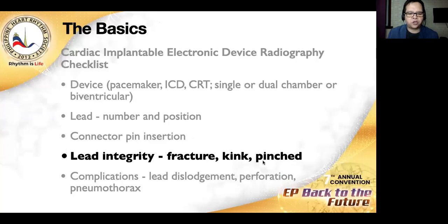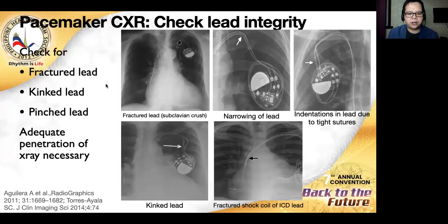Now, lead issues, specifically lead integrity, are also commonly assessed by X-ray. So whether you're looking for fracture, kinks, or a pinched lead, that can be assessed by the X-ray. So the checklist includes looking for a fractured lead, a kinked lead, or a pinched lead. And for this, it is imperative that adequate penetration of the X-ray is done in order to be able to visualize the structure of the leads.